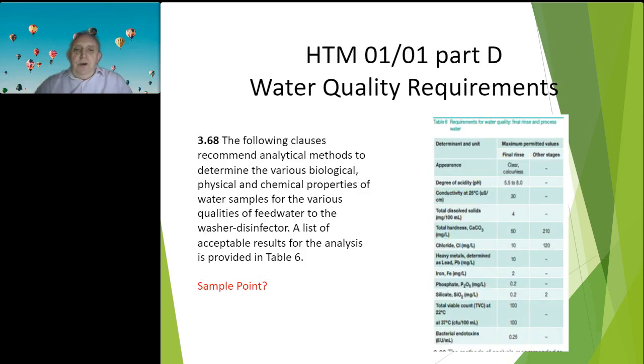So here's an example of what is in HTM 0101 Part D. As you can see, the limits in there are quite precise. So where do we sample this water? Do we sample it at the purification plant? Do we sample it at source? Do we sample it at the washer disinfector? Well, ideally, you should have information of all parts of the process. We need to know what sort of water is coming into the premises. We need to know our purification plant. We need to know, is it doing what it should be doing, and we need to know the quality of the water at the washer disinfector.